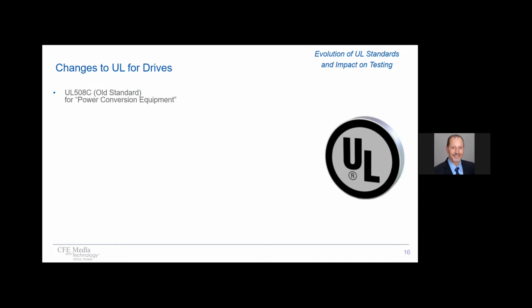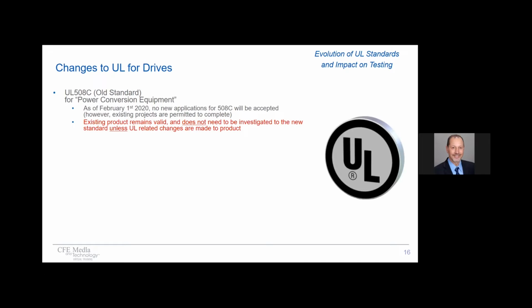For decades, UL 508C has been the standard against which all drive suppliers have been evaluated. As some of you know, UL 508C has been replaced with a different standard going forward. As of February of last year, UL is no longer accepting any new applications for drive products under 508C. However, they are allowing existing projects to be completed. Existing products do remain valid, and they don't need to be investigated to the new standard unless, as I mentioned before, there were significant design changes in those products. Then they would have to be reevaluated to the new standard.